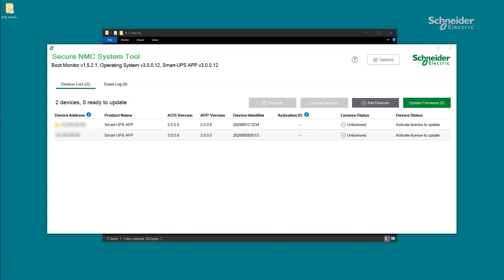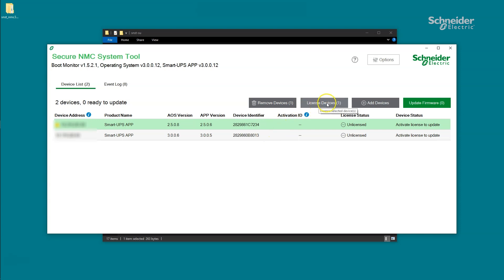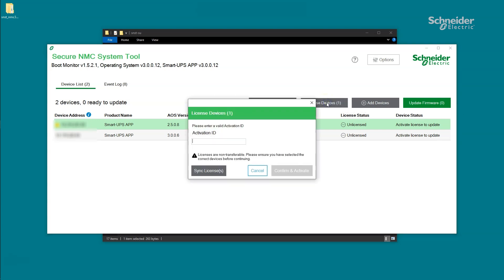Now that you've added devices to the Secure NMC System Tool, you can now activate licenses for the selected NMCs. Click on the NMCs in the device list and click License Devices. If you have more than one NMC in the device list, use Ctrl plus click to multi-select. Enter the Activation ID from the purchased Secure NMC System subscription and click Confirm and Activate. If you have the Secure NMC System Tool installed on another PC and want to check if any of the NMCs are already licensed, you can click Sync Licenses to do so.